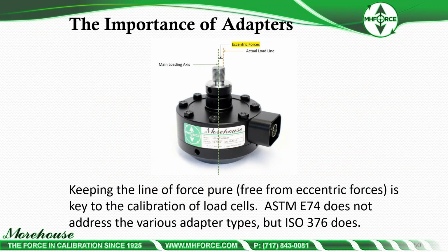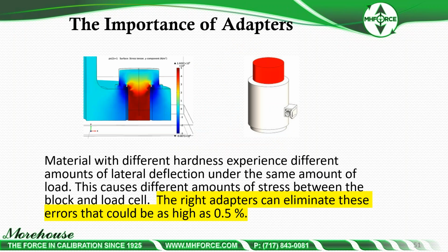So if we go back to ISO 376 and just generally any force calibration that you do or that your lab is conducting, the importance of adapters is keeping the line of force pure, free from eccentric forces. It is key to calibration of any load cell or any force proving instrument. ASTM E74 does not address the various adapter types, but ISO 376 does give guidance.